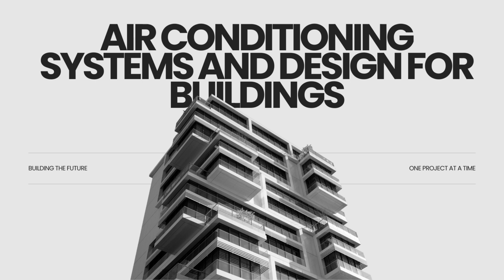Okay, here's where it gets really interesting. Let's put these numbers to work. The source gives a sample project, a small office that measures 5.00 meters by 6.0 meters. How do we determine the aircon requirement for this space using these shorthand calculations, and what are the practical implications of the different options? Great question. Let's walk through step 1. Solving for the cooling capacity needed for this room. We can use either the HP or the BTU method, and they should give us a reasonably consistent result for a preliminary estimate. Okay, let's try the HP method first.